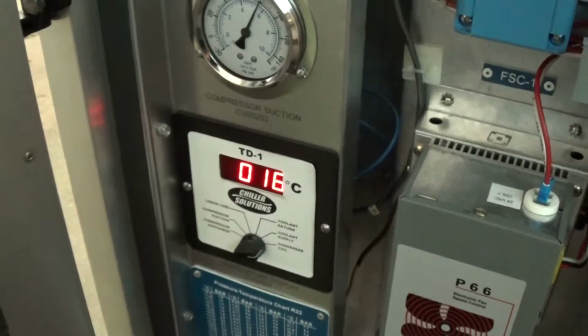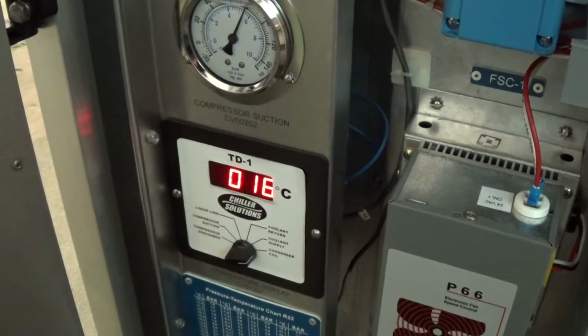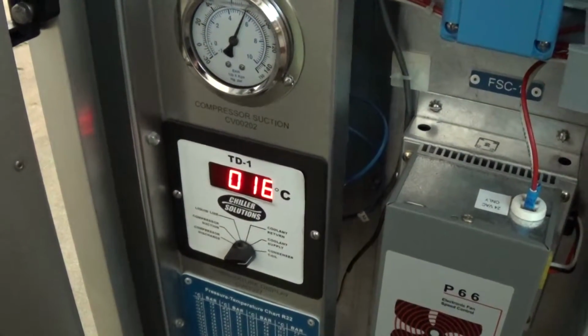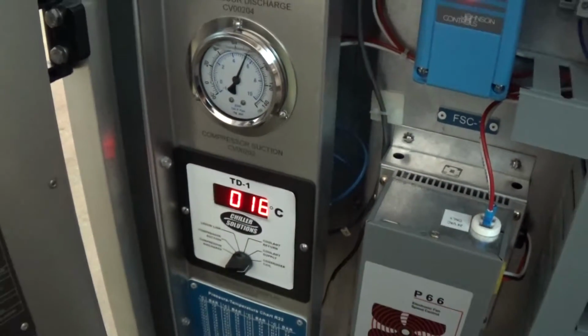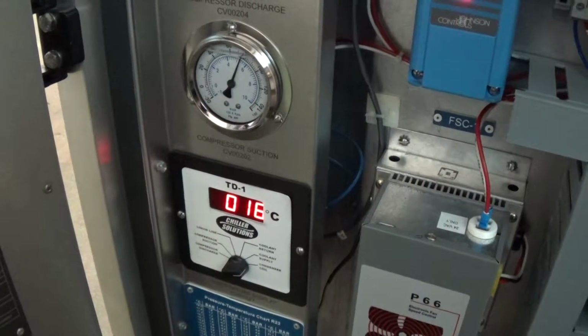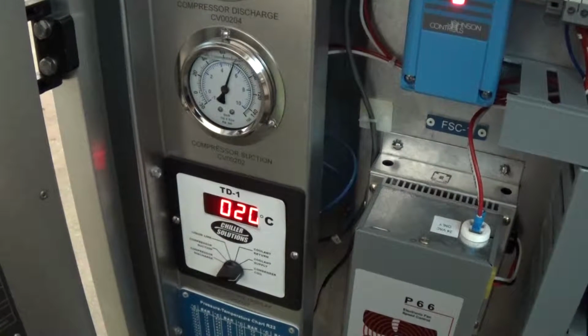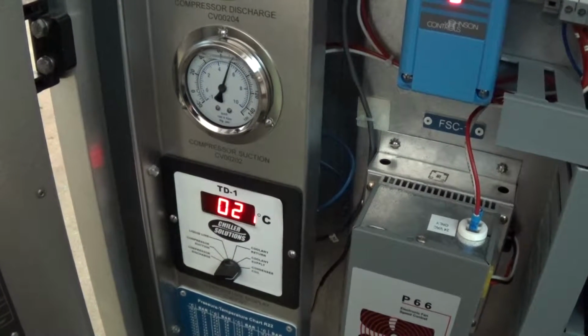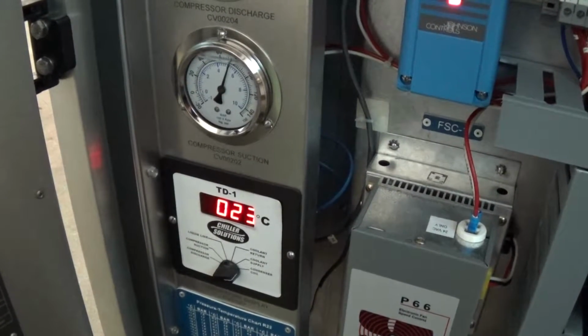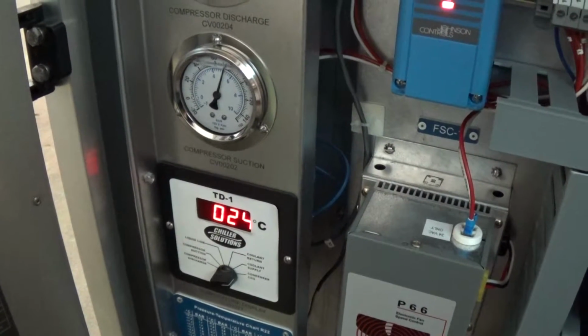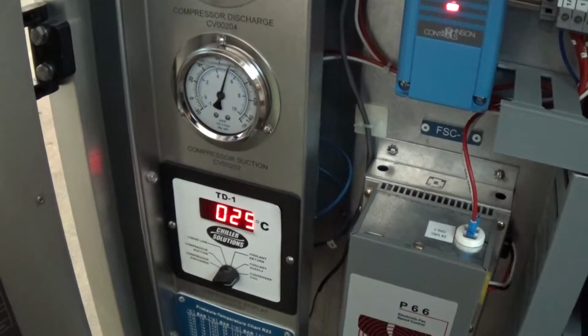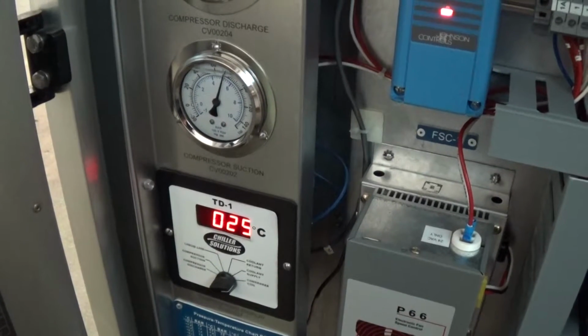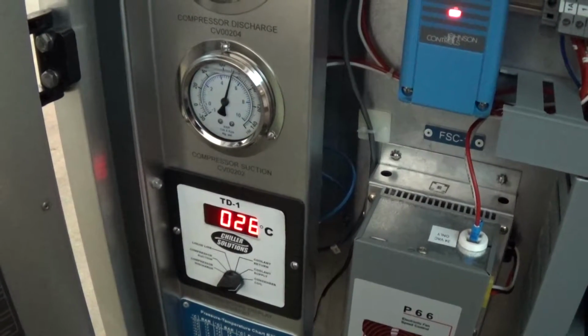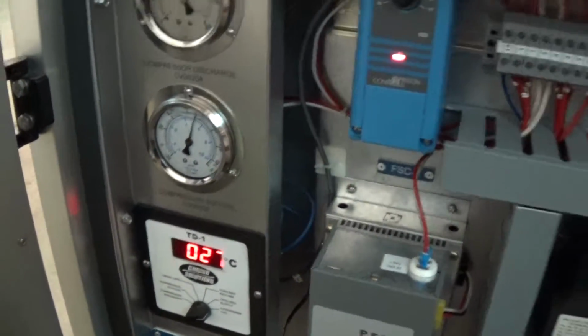We can tweak it. Once we meet our set point, we want to chill at about 28 Fahrenheit, which is -2 degrees centigrade. You don't want to go much colder than that. In fact, if you can get away with a little bit warmer, that's ideal. You want to have it at the warmest set point temperature that satisfies your brewery glycol loop. Because the colder you run, the harder the compressor is going to work, and at the end of the day, the less BTU capacity you actually have.